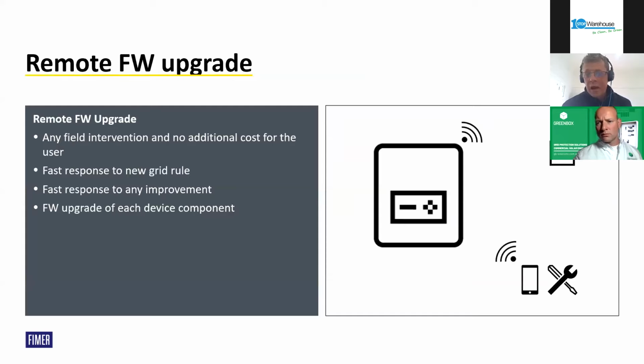Once connected, there are some great tools. You have full access to parameters, and there are a couple of different levels — the installer has administrative rights, so they can connect and change all the parameters, while the customer can connect to the inverter with fewer privileges, more like a site owner with read-only access. As an installer with administrative rights, you have access to all the grid codes and grid parameters, and you can do firmware upgrades remotely as well as locally.